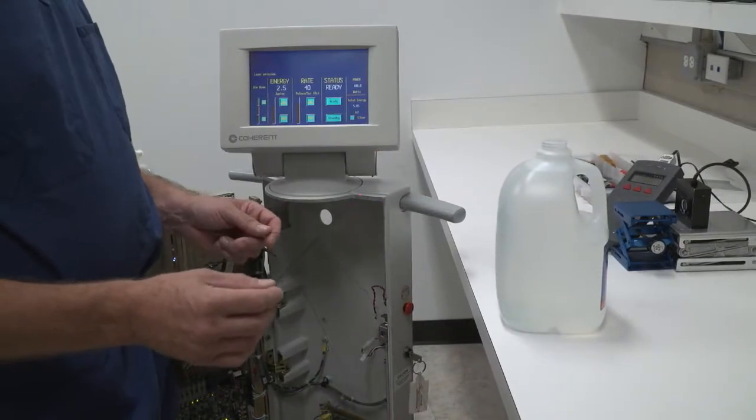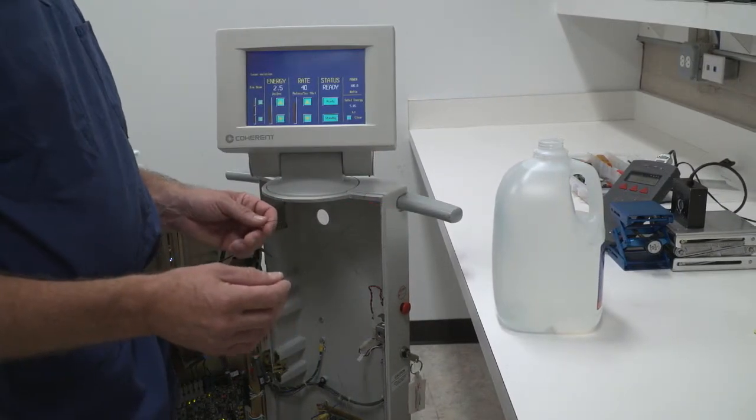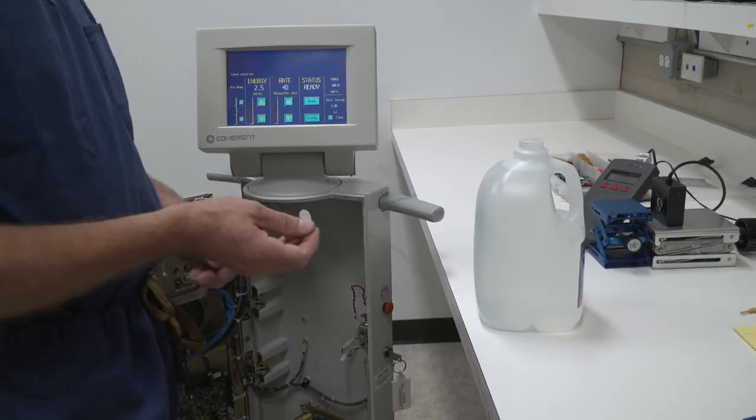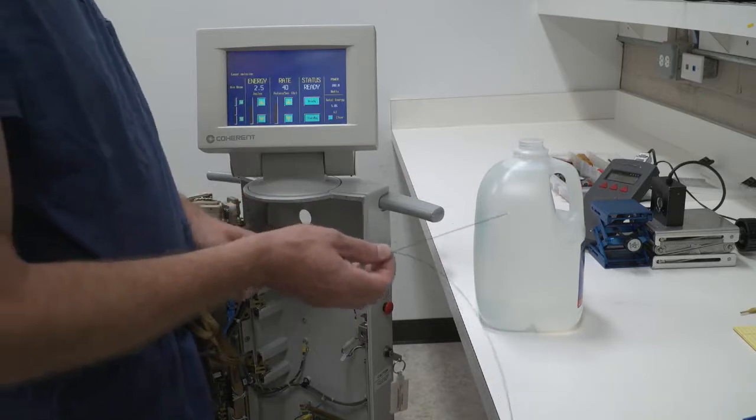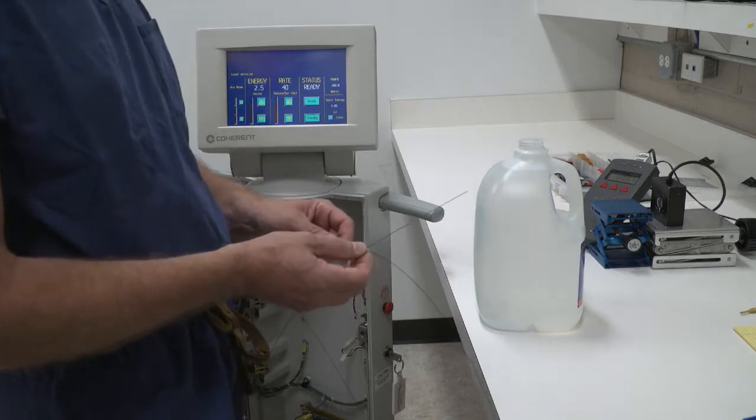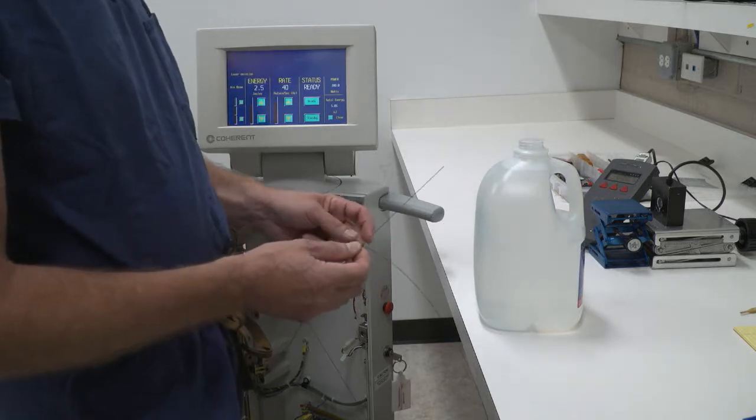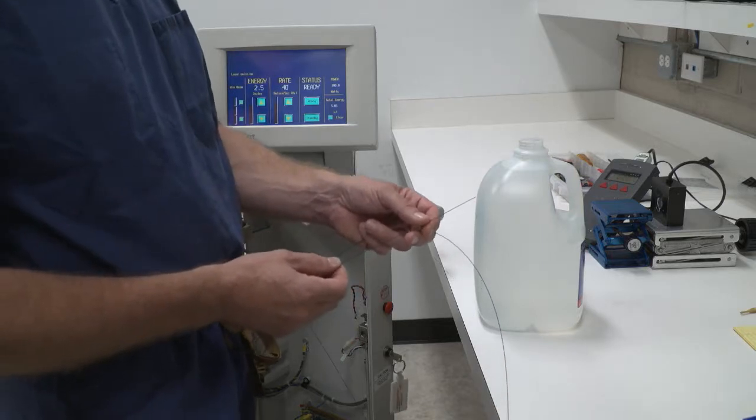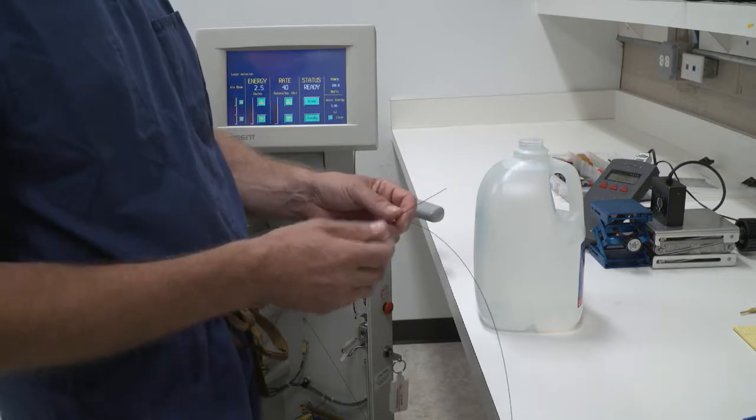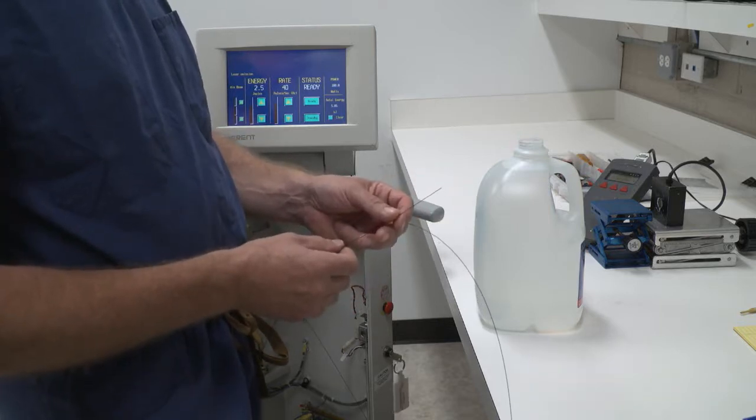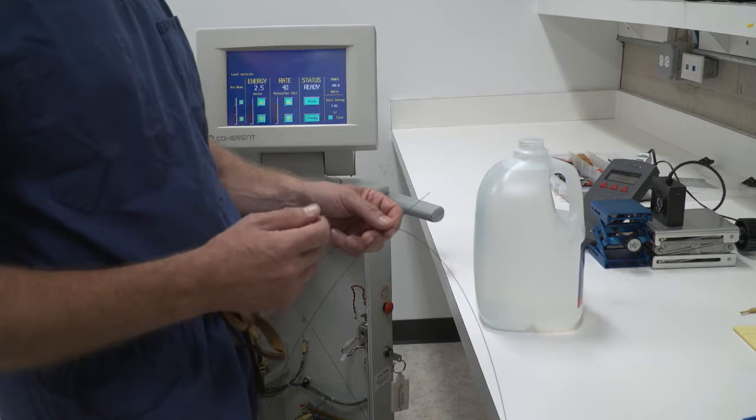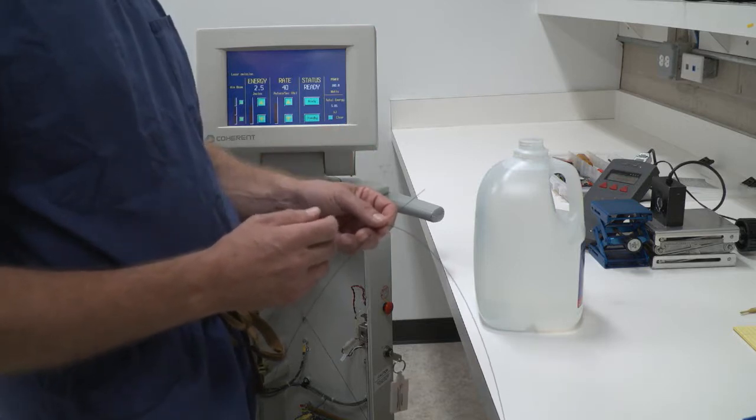Now that I know that the laser has been completely aligned and calibrated, I want to functionally test the laser. If I were to turn the energy up to a higher level, this laser goes up to 100 watts and fired into this fiber in mid-air, the energy coming through the fiber would melt the tip of the fiber and destroy the fiber.